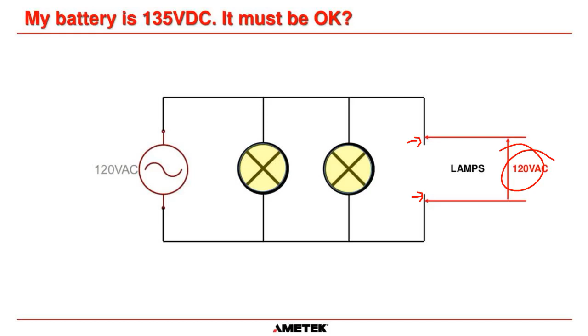Now let's say we removed one of those lamps, unscrewing it. If you went to that lamp fitting and measured between the live and the neutral, you'd still measure 120 volts. It's still live, because just because the lamp is not there, you still have voltage available, since they're all in parallel.